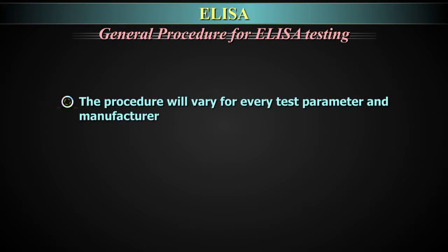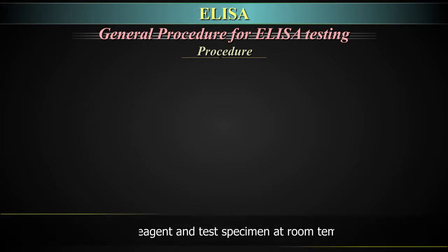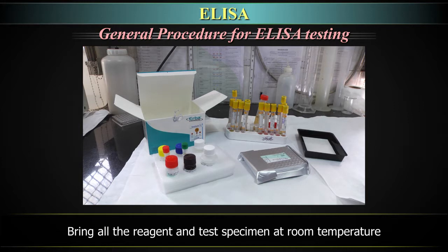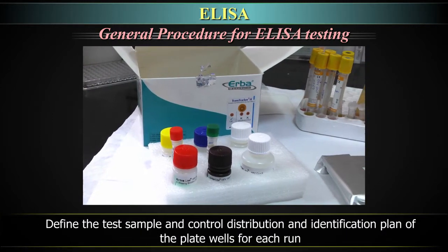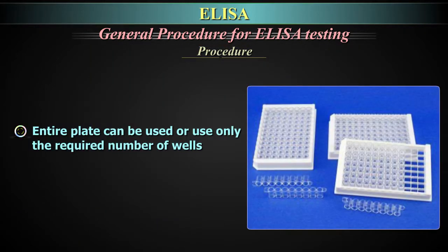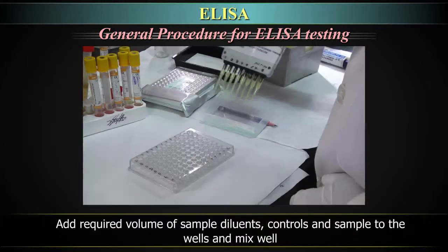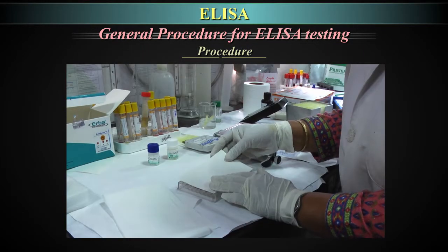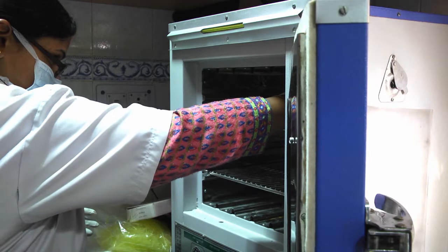The procedure will vary for every test parameter and manufacturer. The procedure to be followed should be based on the manufacturer's instructions and should be validated before being put in use for patient samples. The general procedure includes the following steps: bring all reagents and test specimens to room temperature; define the test sample and control distribution and identification plan of the plate wells for each run. The entire plate can be used, or only the required number of wells. Balanced unused wells can be wrapped and stored. Add required volume of sample diluents, controls and sample to the wells and mix well.